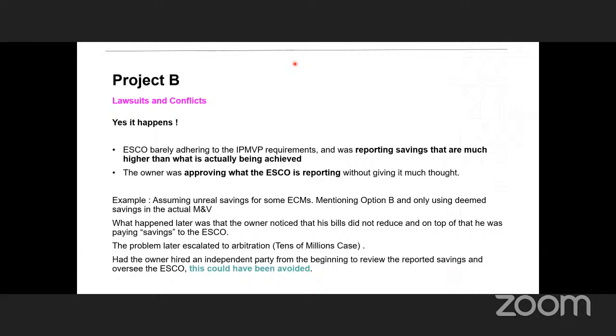So some of the examples here: assuming unreal savings for some energy conservation measures, mentioning option B and only using deemed savings. Option B requires putting in meters and measuring all the parameters. They had nothing. They were just basically saying, I'm going to install a VFD on this pump, I'm going to save 60% of its energy. And the baseline was also calculated. Some of them were measured for small periods of time. And they come up with the baseline and say, I'm saving 60% of that without any validation from actual site measurements after the implementation.